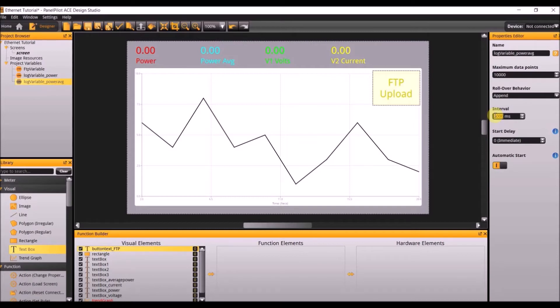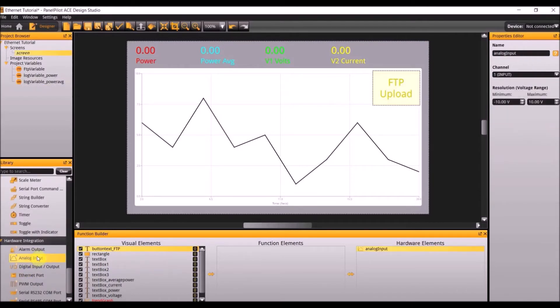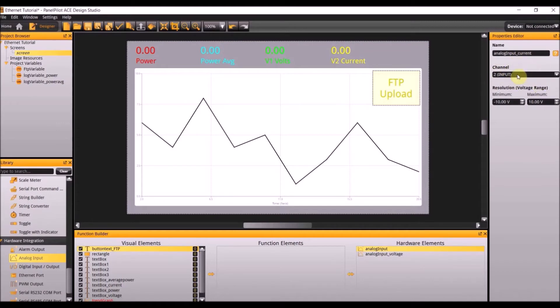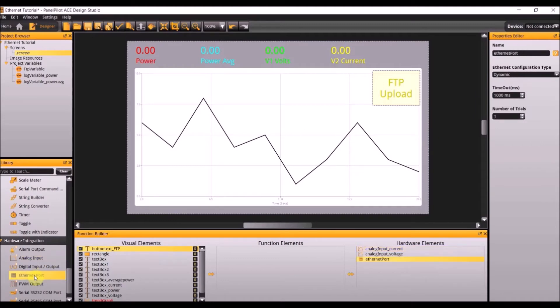Next we will move on to the function and hardware elements. The first hardware element needed is analog input, so go over to the library and add analog input. Name it analog input voltage with a minimum resolution of 0 to 5. Add another analog input, name this one analog input current, make sure the channel is 2, and make the resolution from 0 to 5. The final hardware element needed is an Ethernet port, so add the Ethernet port hardware element. Make the type dynamic, the timeout 1000 milliseconds, and the number of trials 1.